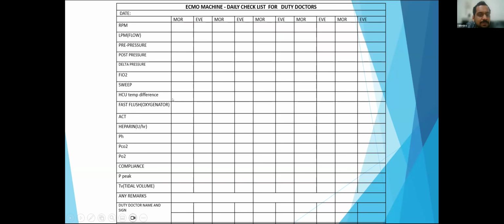If the temperature difference is 0, that means no sepsis. If the temperature difference is more than 1, that means some sepsis is happening. Fast flush done: a fast flush of the oxygenator, whether it is done or not, ACT values, and then the heparin dosage for the corresponding ACT values, pH, PCO2 and PO2 of the patient's ABG. Based upon the PO2, you maintain the flows and FiO2. Based upon the PCO2 levels, maintain the sweep gas flows and the blood flows.